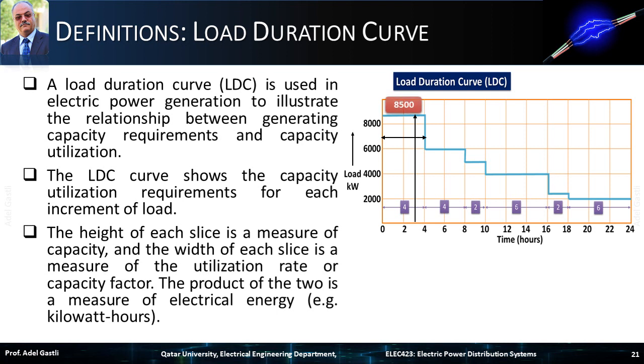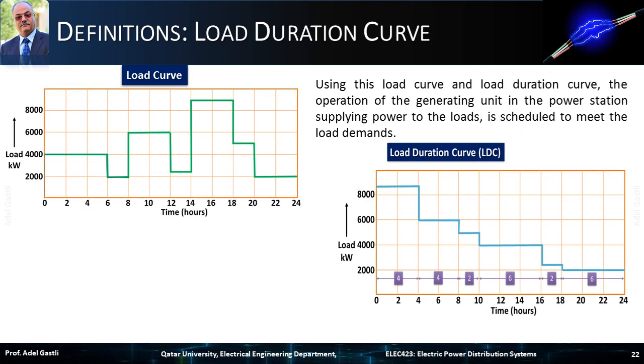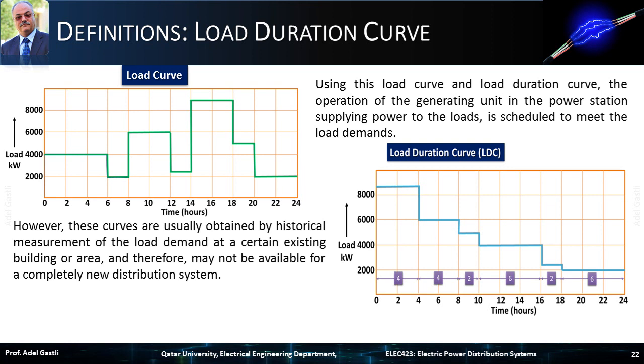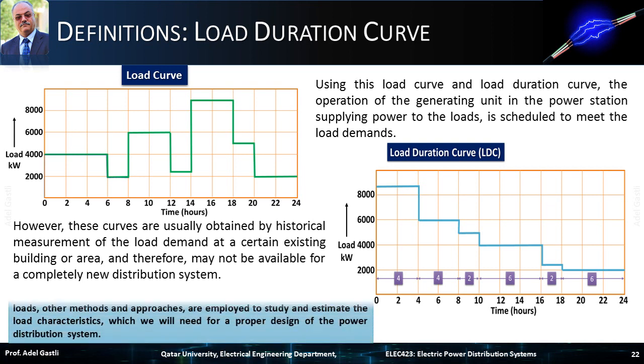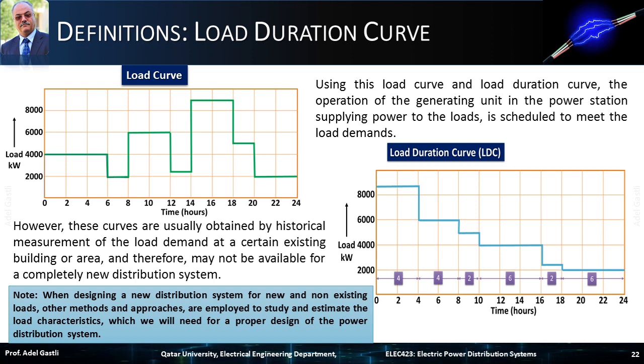For our example, the peak load is 8,500 kilowatts for a duration of 4 hours, and the base load is 2,000 kilowatts for a duration of 24 hours. Using the load curve and load duration curve, the operation of generating units is scheduled to meet load demands. However, these curves are usually obtained by historical measurement of load demands at an existing building or area, and may not be available for a completely new distribution system. When designing a new distribution system for non-existing loads, other methods and approaches are employed to study and estimate the load characteristics.